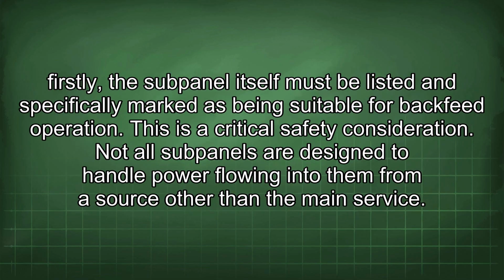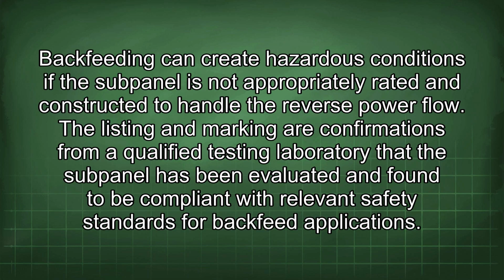Firstly, the subpanel itself must be listed and specifically marked as being suitable for backfeed operation. This is a critical safety consideration. Not all subpanels are designed to handle power flowing into them from a source other than the main service. Backfeeding can create hazardous conditions if the subpanel is not appropriately rated and constructed to handle the reverse power flow. The listing and marking are confirmations from a qualified testing laboratory that the subpanel has been evaluated and found to be compliant with relevant safety standards for backfeed applications.